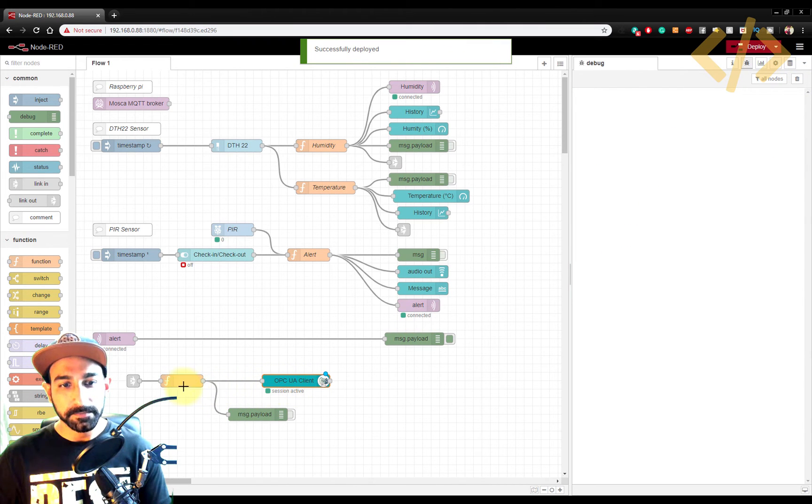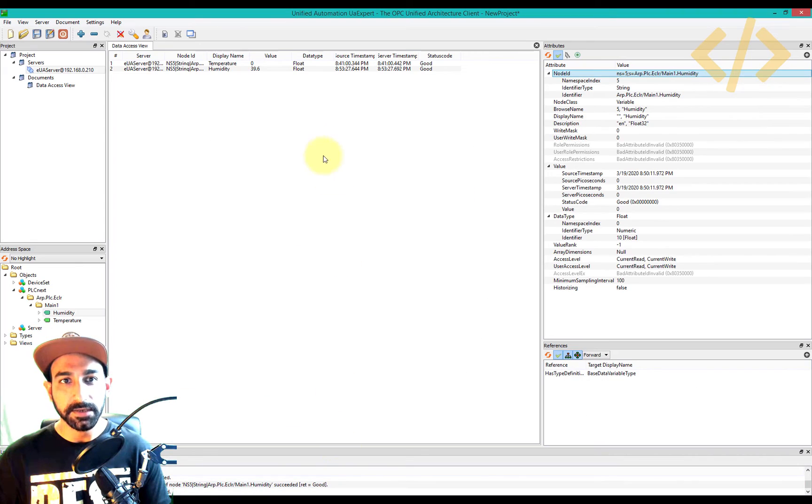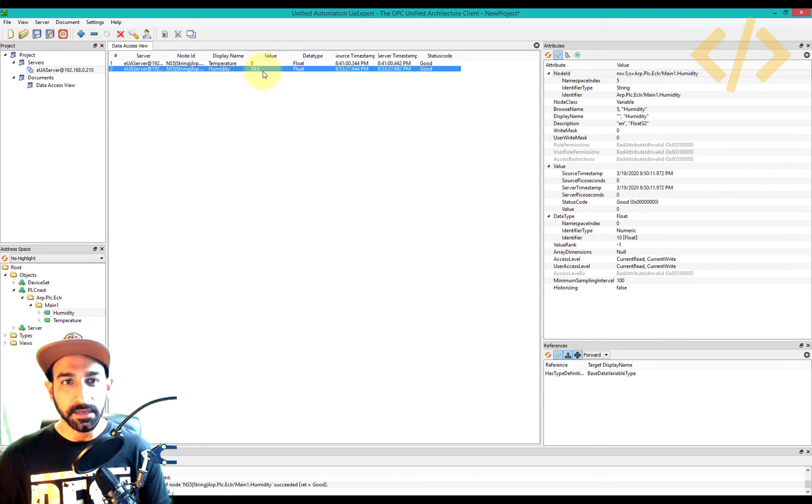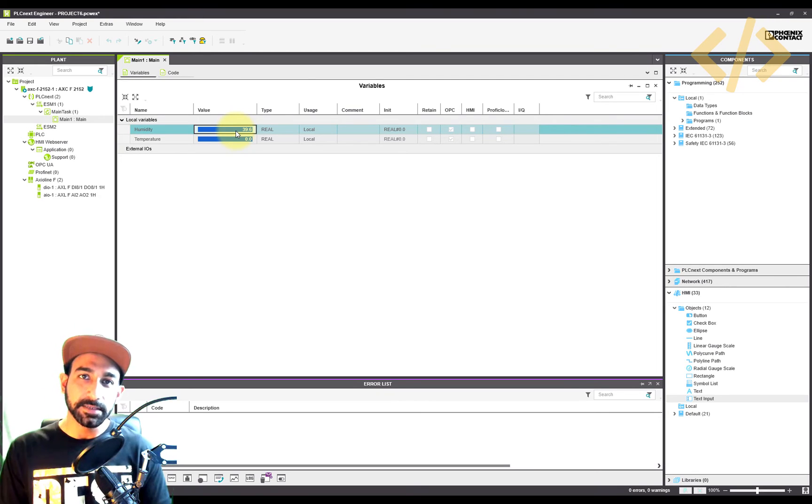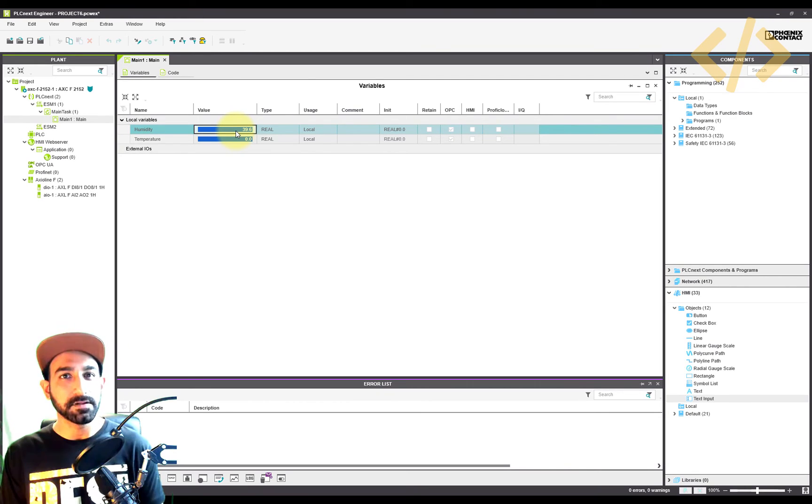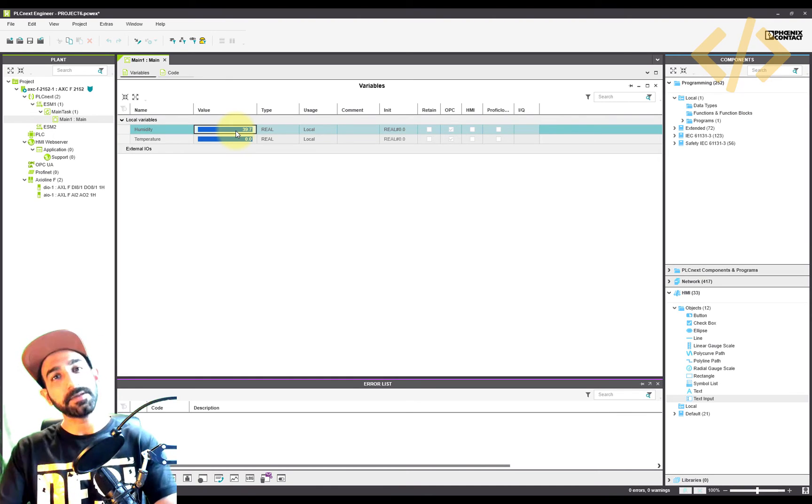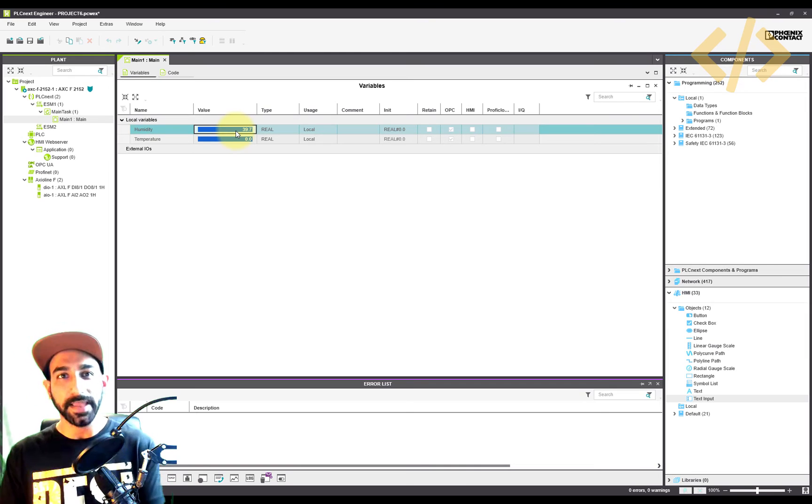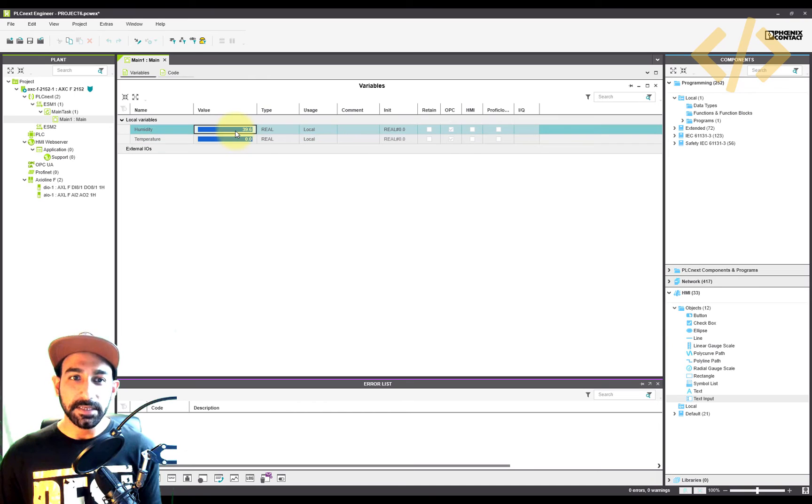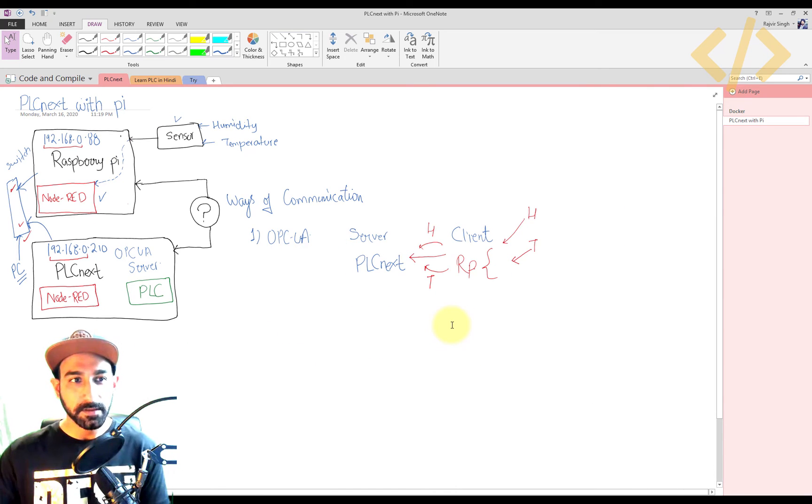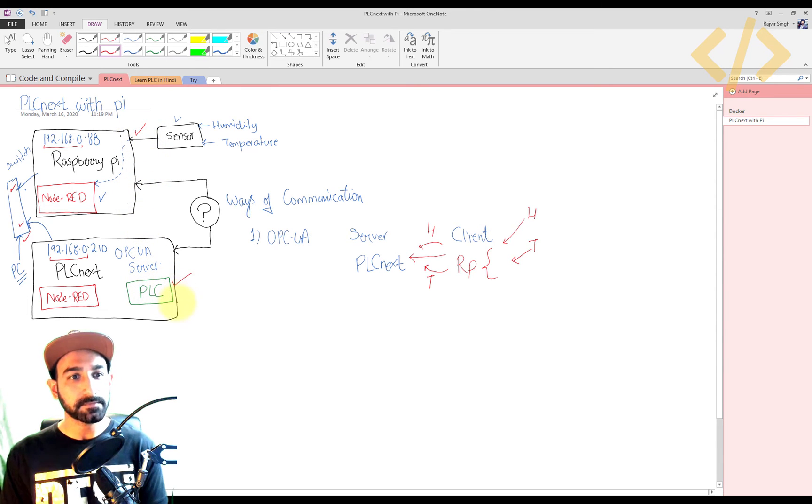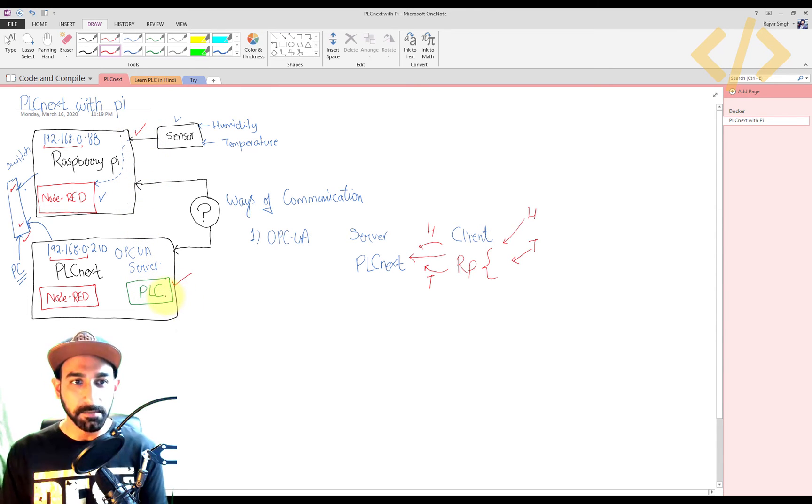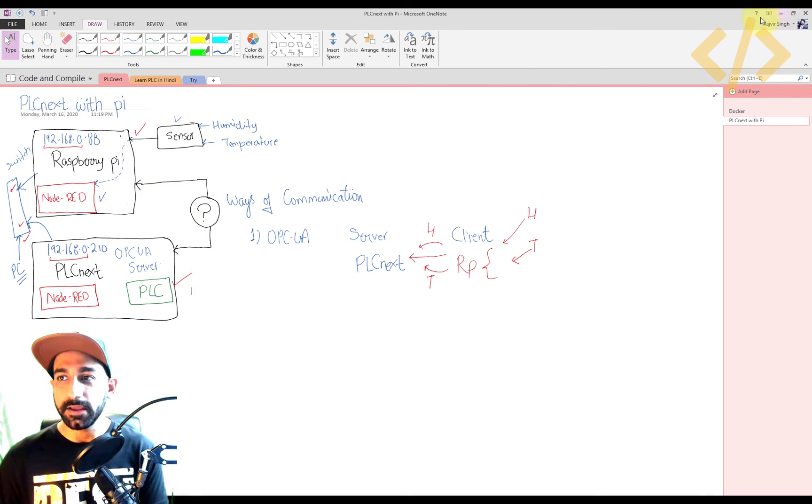This time it should work. So now this is moving the value, it says active writing. And now let's go inside, check UA Expert. And we see the values coming: 39.6. You can also see that in PLCnext. So humidity is coming now in the PLC. So this is just an example that if you have different controllers having different sensor values, and you don't want to take the wire from the sensor to your PLC and measure it again, no, just talk to the controller via OPC UA. So I'm just getting the value of the sensor which was connected to Raspberry Pi. Now the value is coming to PLC in a data block. So the sensor value is traveling via OPC UA to your PLC. This is one way.